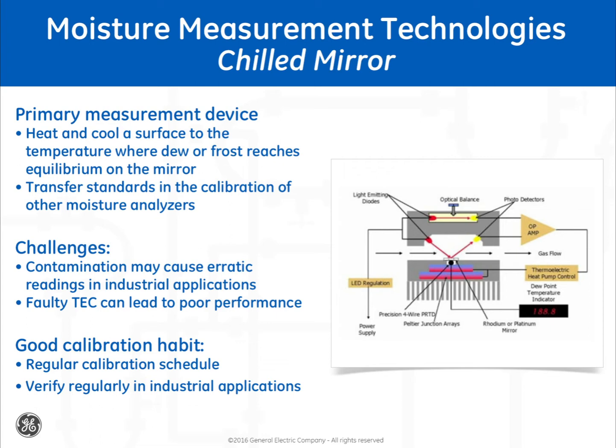Contamination can impact the performance of this analyzer, as can fault with the thermoelectric coolers. In the field, these can be verified using any of the previously mentioned techniques, especially when these are used in industrial applications, as opposed to clean and controlled laboratory environments. This is not a comprehensive list of all the trace moisture technologies. Calibration or verification requirements for other technologies can be similar to those previously mentioned, with similar benefit.